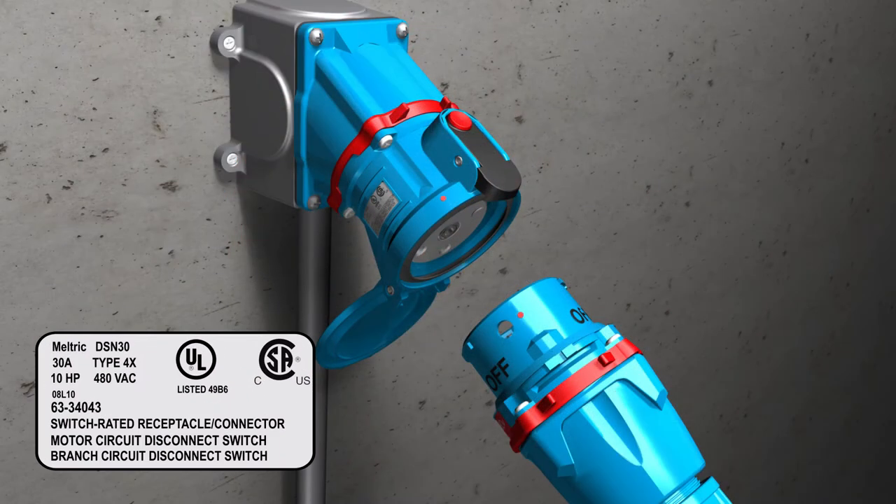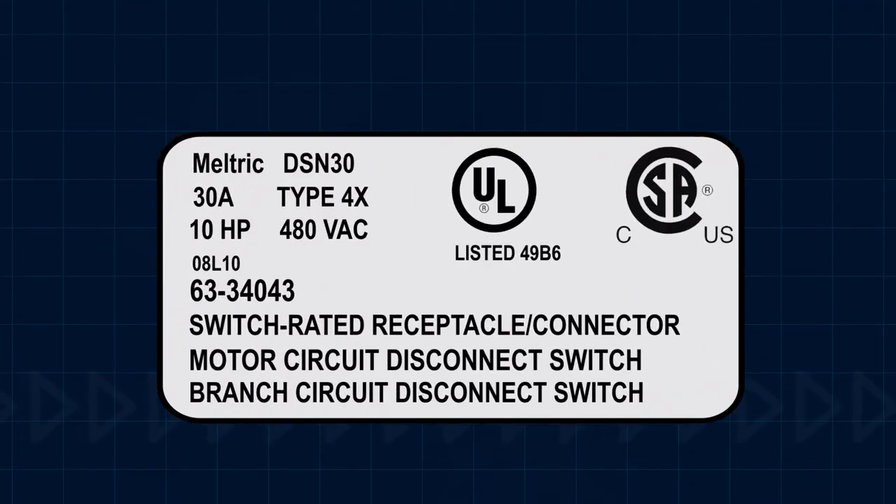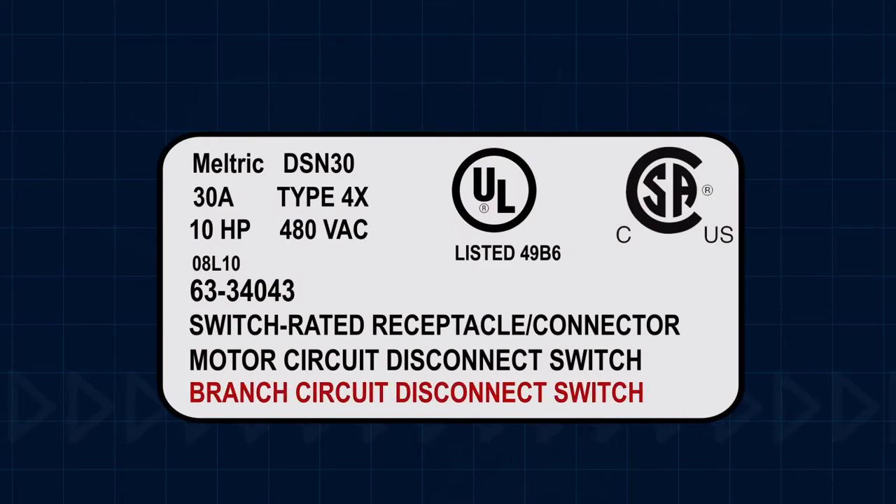As stated on the device label, Meltric switch rated plugs and receptacles are UL and CSA listed as a motor circuit disconnect switch for applications up to 100 horsepower. They are also listed as branch circuit disconnect switch for applications up to 200 amps.